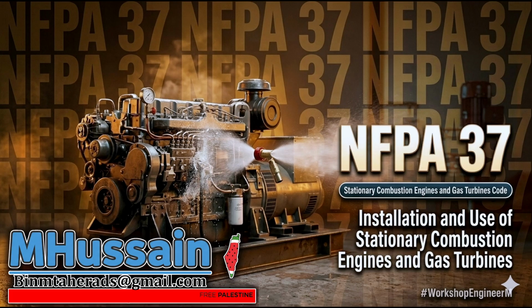Exactly. The exhaust pipe, however, has already left the engine block. It's radiating infrared heat into the room. Oh, so it's not hurting the engine, it's threatening the room. Right. If a technician brushes against it, it's instant third-degree burns. If someone leaves a cardboard box nearby, the radiant heat will ignite it. So the blanket keeps the surface safe to touch and forces all that thermal energy to travel outside the building? Precisely. It traps the heat in the gas stream itself.